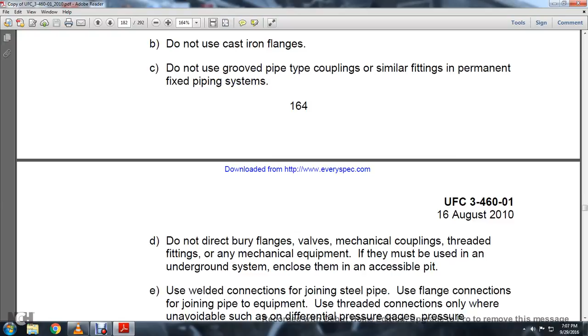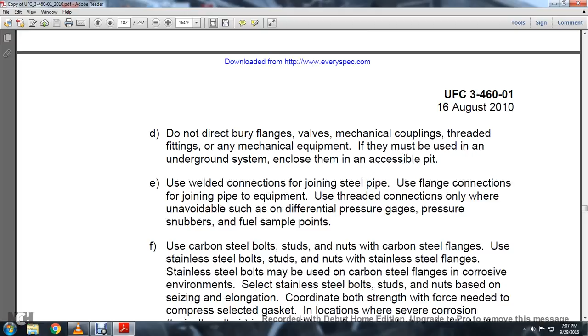Do not directly bury flanged valves, mechanical couplings, threaded fittings, or any mechanical equipment. If they must be used in an underground system, enclose them in an accessible pit. Use welded connections for joining steel pipe. Use flange connections for joining pipe to equipment. Use threaded connections only where unavoidable, such as differential pressure gauges, pressure gauge connections, and fuel sample points.